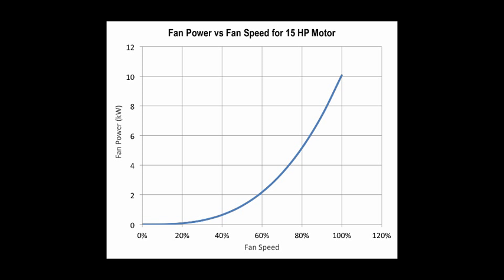This chart shows the relationship between fan power and fan speed for our 15 horsepower example. You'll notice that this relationship is not linear, but it's in fact cubic.